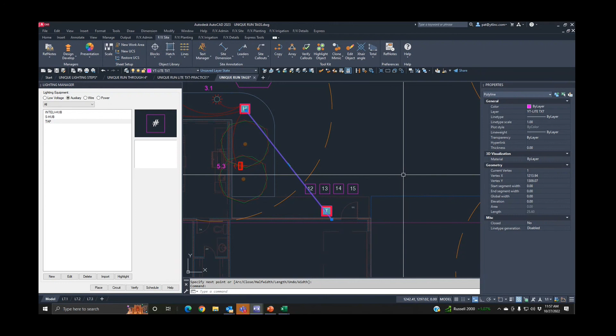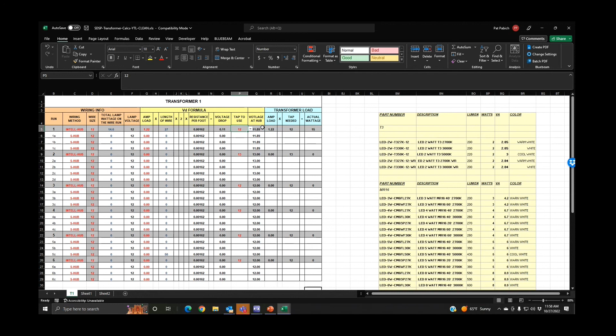On our IntelliHub run number 1, if we use a wire size of 12, we have this wattage or VA, and we connect it to the 12 tap. This spreadsheet has different tabs you can connect to. Our voltage at the hub is going to be 11.89. That's perfect. We want a number no lower than 10 and no higher than 15. In our office we don't allow the guys to go below 10.5, but that's just the way we do stuff. So a wire size of 12 going to the 12 tap gives us 11.89.